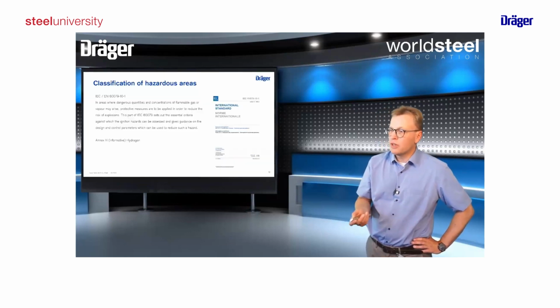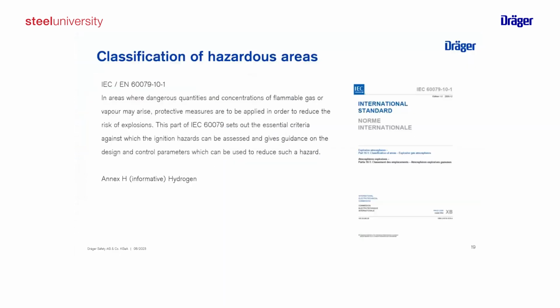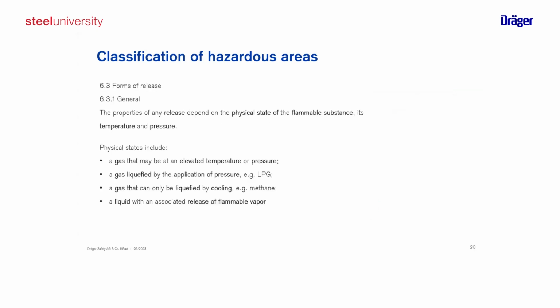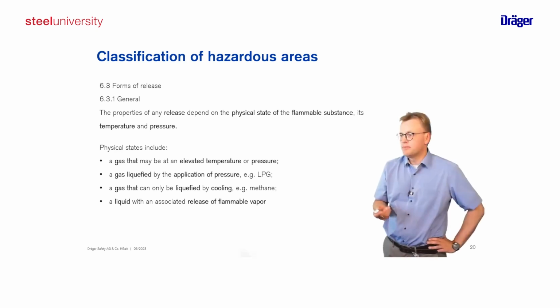And for this, we have the IEC standard 60079-10-1, which is a good guidance to run through. And interesting is there's a separate chapter about hydrogen, so special measures which should be considered when you deal with hydrogen in your application.